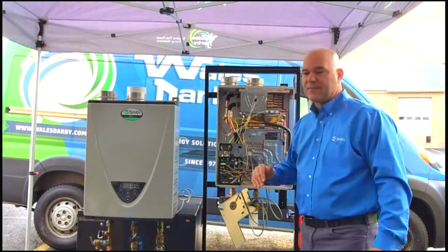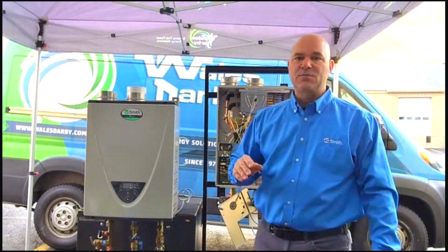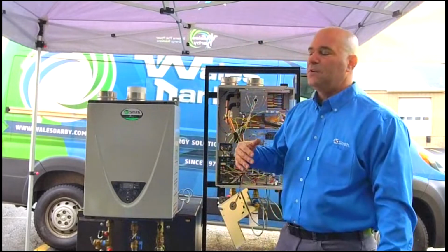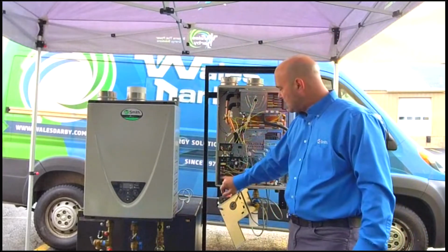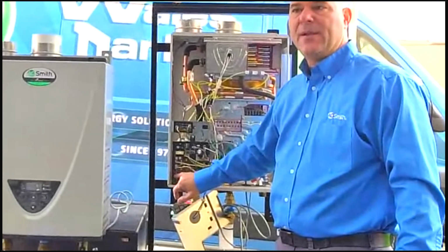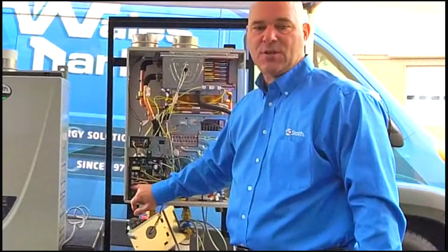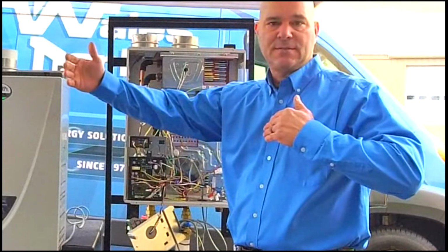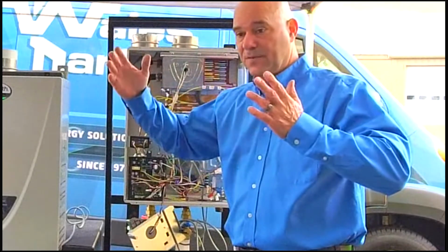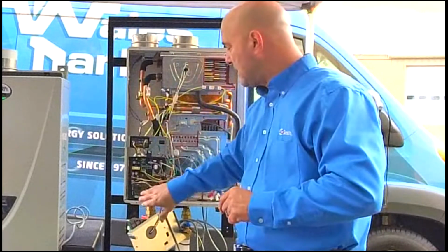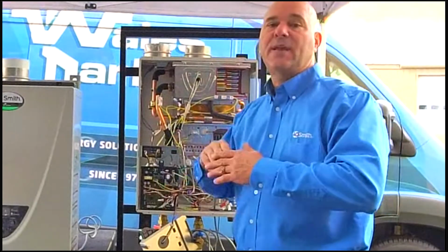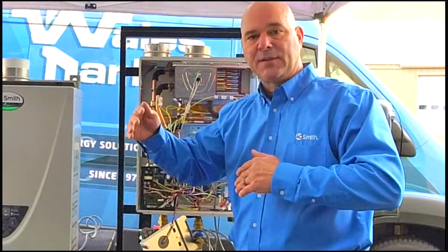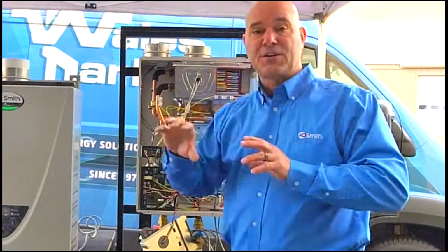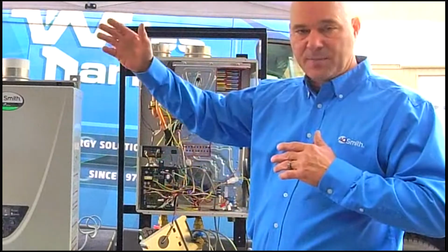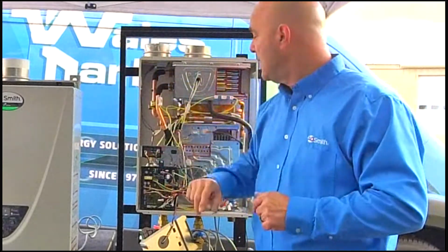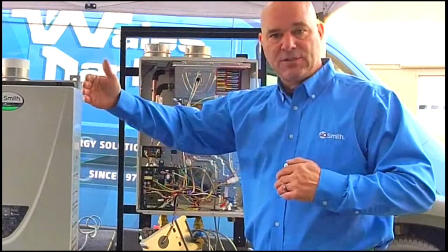On this unit, it comes out of the box ready to vent between 0 and 25 feet. If you go beyond 25 feet, there's dip switches here in the control. In the manual, it will tell you what dip switch to change based on your venting distances. So if your venting distance is full, you're going to go in there, make a couple dip switch changes, and that will automatically increase the blower's capability to offset the additional friction of the PVC, polypro, Centrotherm pipe, whatever it is. It will offset that additional footage.